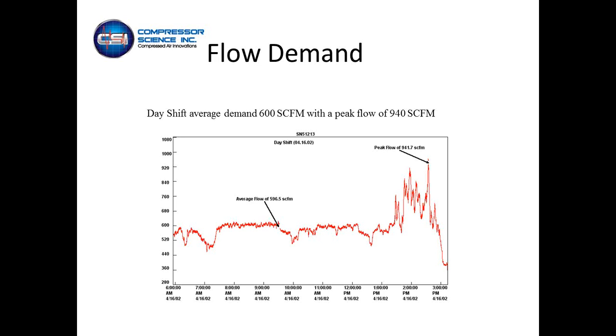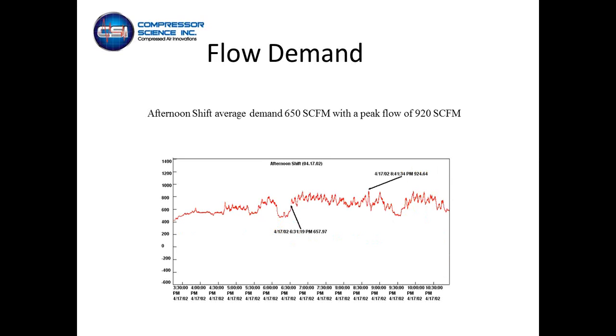The other thing we can measure with the flow, obviously customers that we audit will have fluctuating demands throughout different shifts. This gives you an example where we can look at the average flow throughout a day shift. We can look at the peak flows. What are those peak flows? Are they short periods of velocity surge, or are they sustained flows? What is causing those in production, and can we somehow balance those out or take those out with either storage or changing somehow that process?